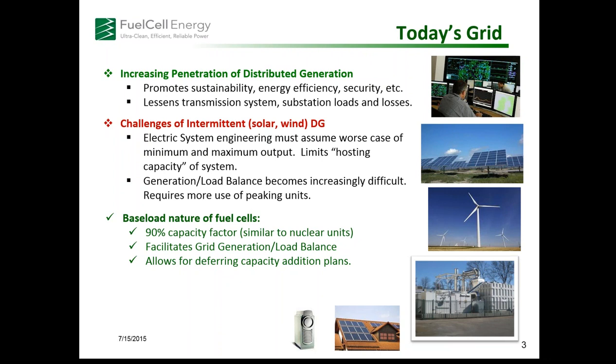One of the challenges, especially with intermittent distributed generation such as solar and wind, is that when these interconnections come through, the utility has to assume the worst case of minimum and maximum output. As Andy was talking about, that's referring to capacity factor. So if you wanted to interconnect a 1 megawatt PV system, over the course of a year it would only put out an average of 200 kilowatts. But as far as the utility is concerned, they have to design everything to the 1 megawatt level, even though they're only getting a quarter of that energy over the year. That ends up limiting the hosting capacity of the system—you're tying up some of that capability for the nameplate of that power plant.